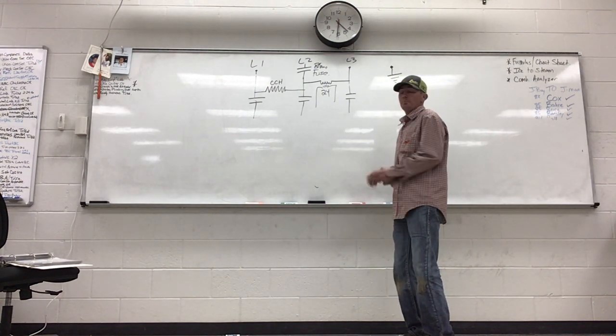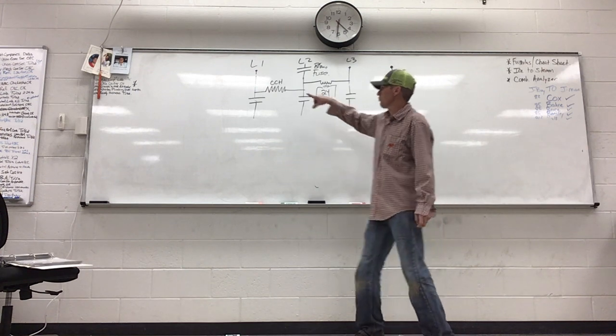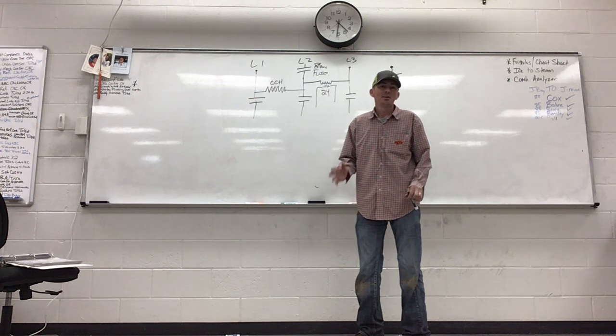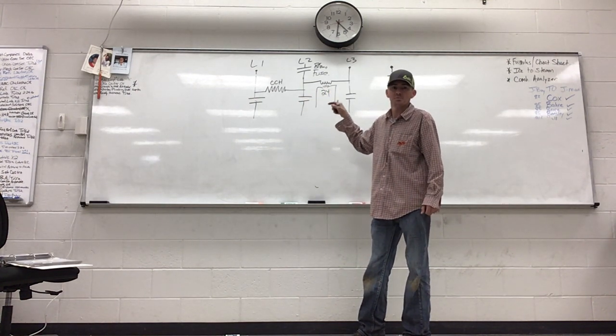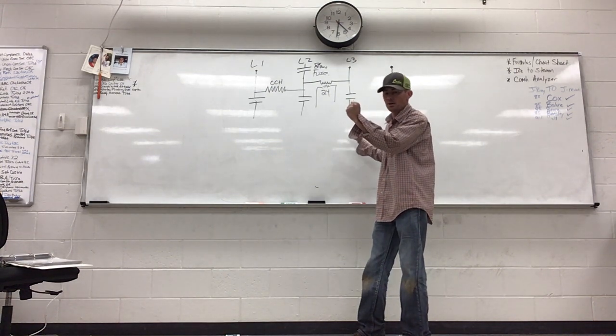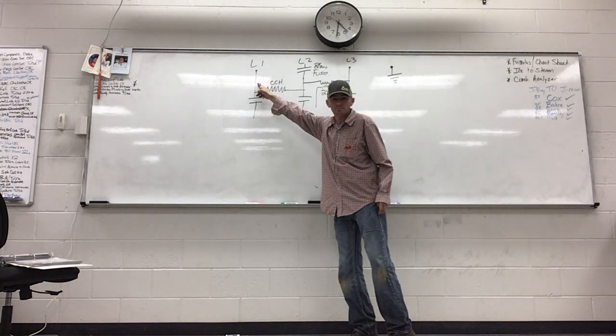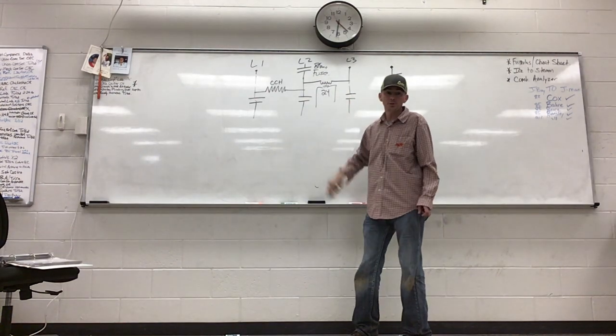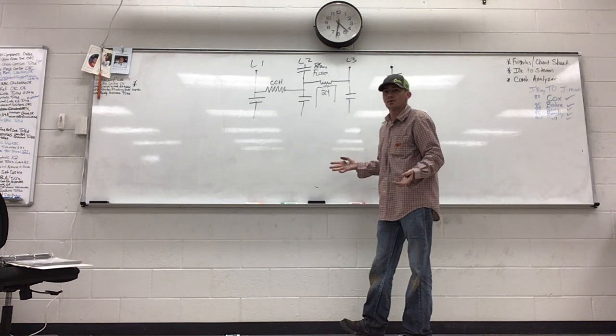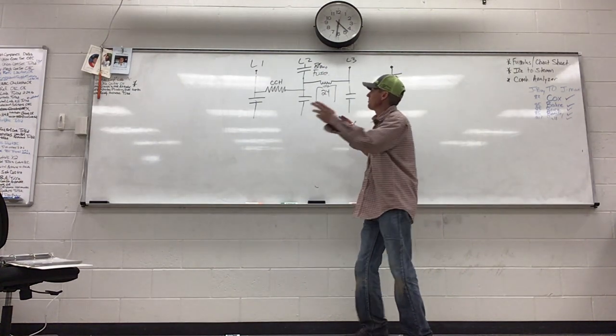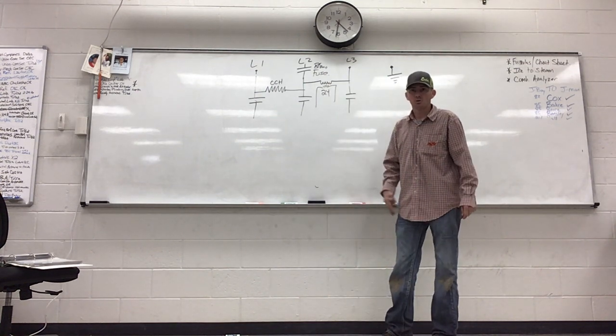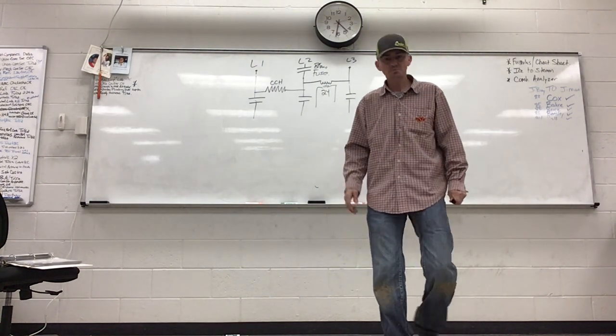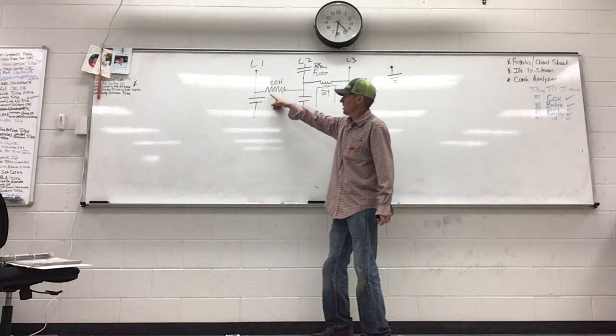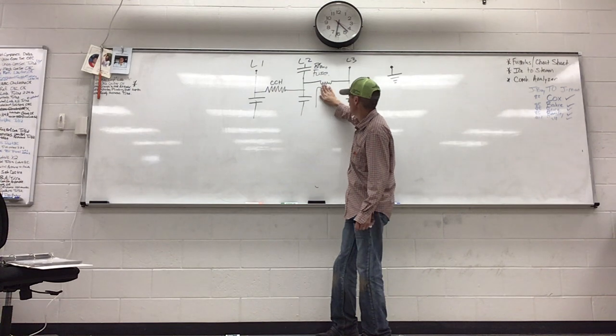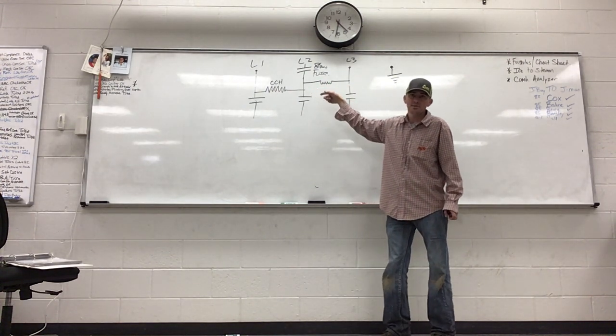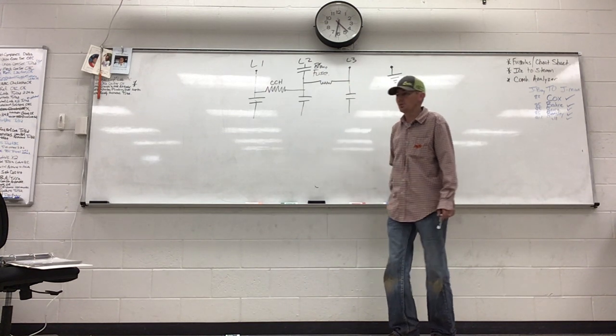Okay. What'll happen, and I get this call quite a bit, people are like, oh, I got weird voltage, I got 208, and I got 120, but then here's the kicker. They'll say, when I check each leg to ground, they're taking each leg and comparing it to ground, they're like, man, I got 120 on L1. I got 120 on L2. I got 120 on L3. When I check each leg to ground, I've got 120 volts. 120, 120, 120. But when I go leg to leg, I've only got 0 or 60 or 120 or some goofy, ghost number. Guys, the reason why is because you have your crankcase heater and you got your primary of your transformer and all this other stuff tied in on the line side of the contactor. This will burn you if you let it. Don't let this burn you. This is something silly, so burn this in your head. Don't let it burn you.